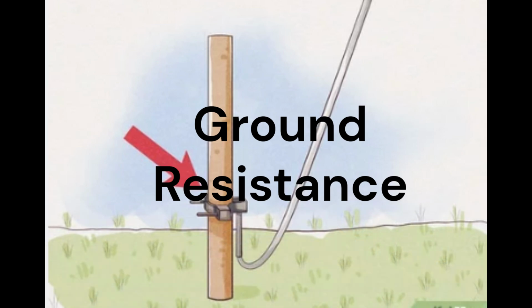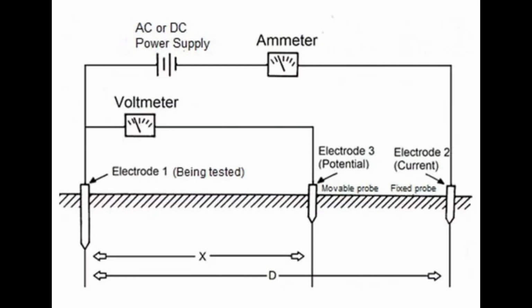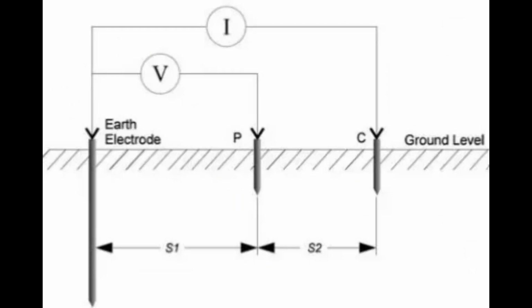So for calculating ground resistance, rather than using a sensor, we have used a method named the fall of potential method. The fall of potential method is widely used as a technique to measure the resistance of a ground or earthing system. In this, three electrodes are used: the earth electrode, the potential electrode, also known as the auxiliary electrode, and the current electrode. The current electrode is placed far from the earth electrode, while the potential electrode is placed at intervals along the line between the ground electrode and current electrode.